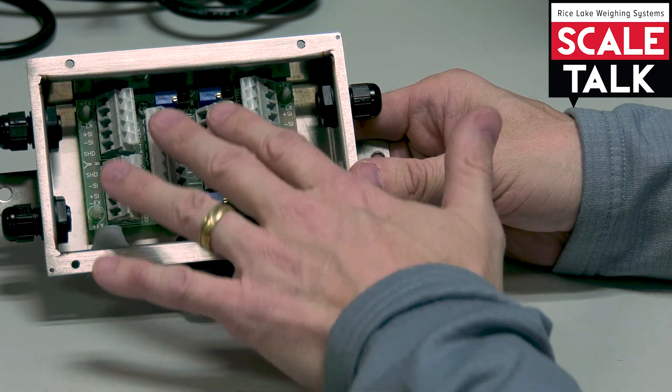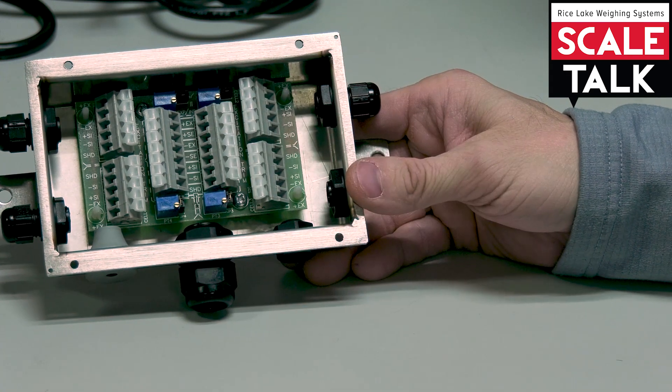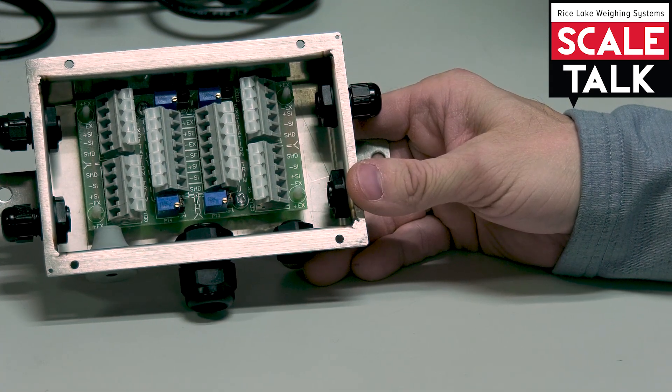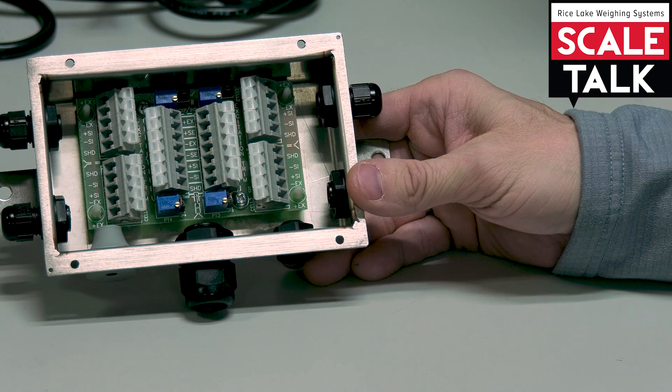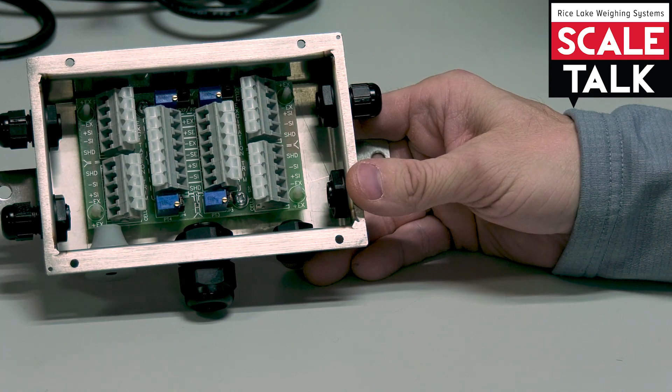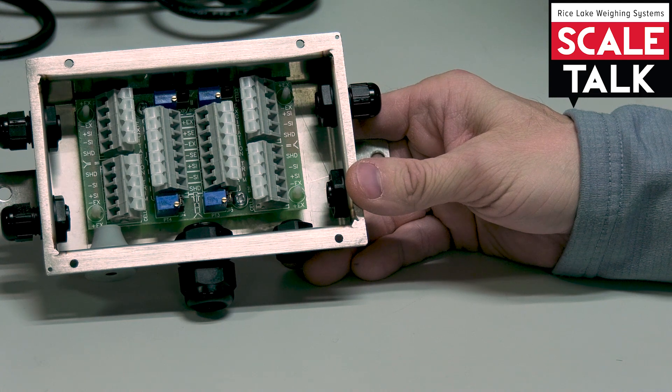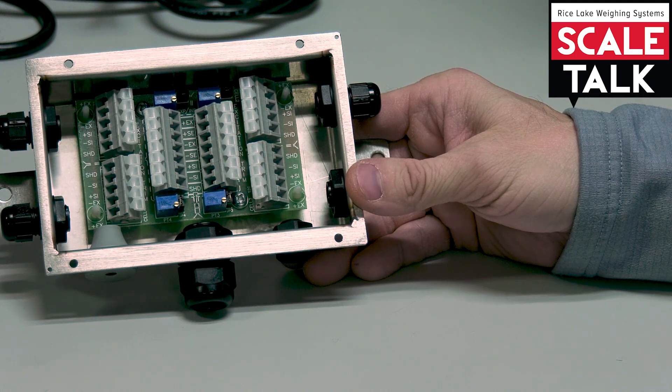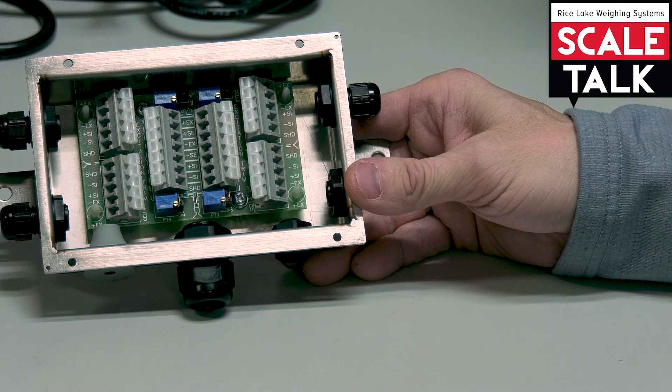And so these potentiometers, the little blue blocks here that are found on that J-Box board, allow me to trim off those differences from cell to cell and create that same signal-to-weight ratio so that no matter where I place the weight on the scale, I'm able to see the exact same weight as I expect.